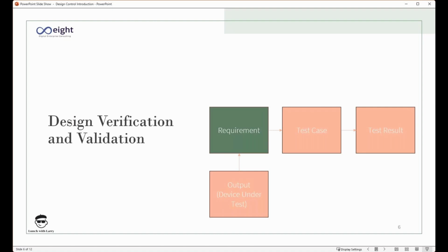So not only do we want to say, here's the evidence that our device complies with the test requirements, but we also want to identify the revision of the output and the revision of the requirement, so we understand as the design changes over time whether we're currently compliant with the requirement revision that has been realized by an appropriate output revision.